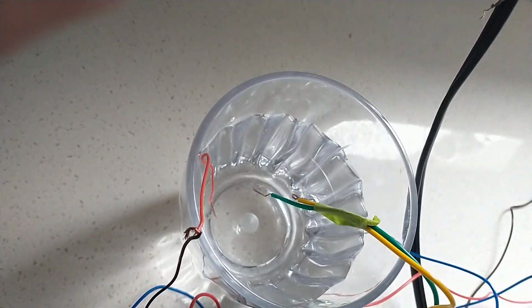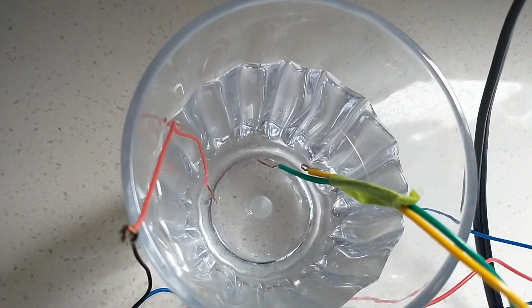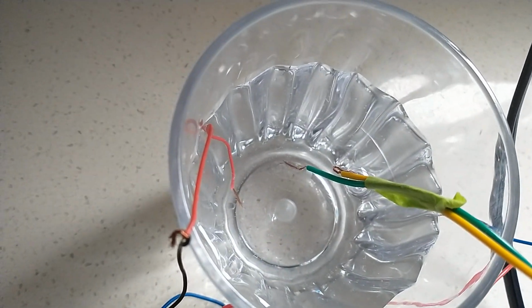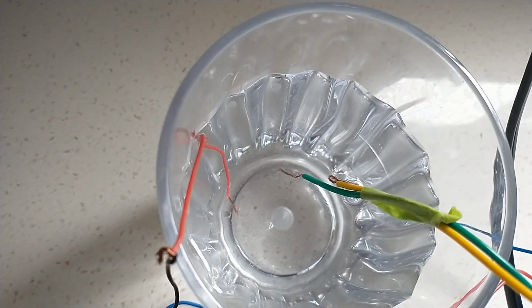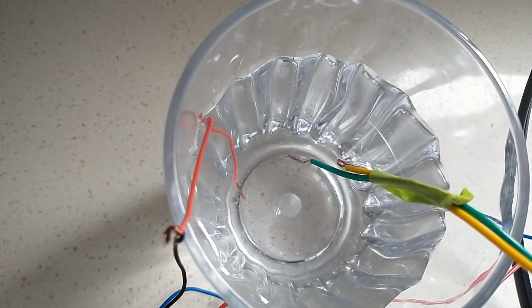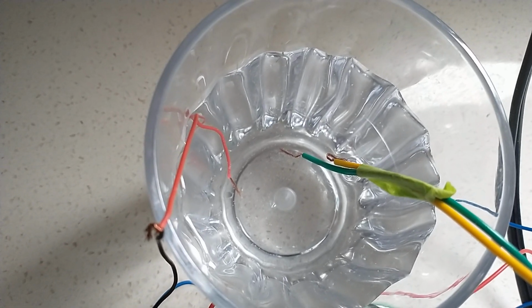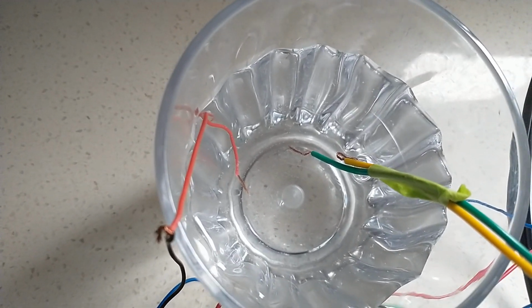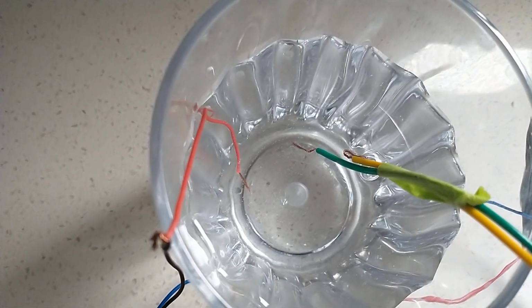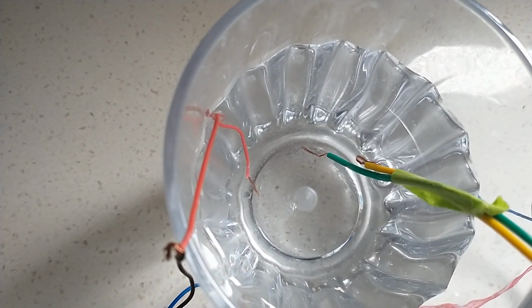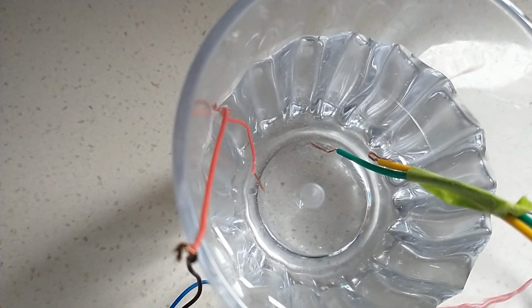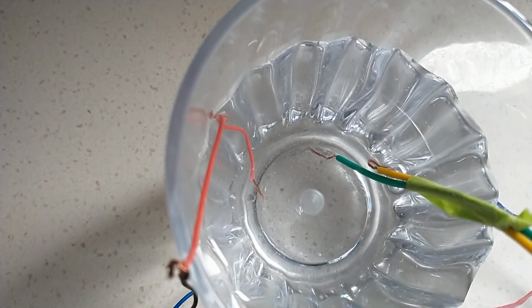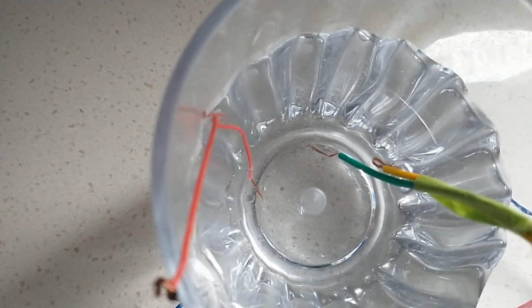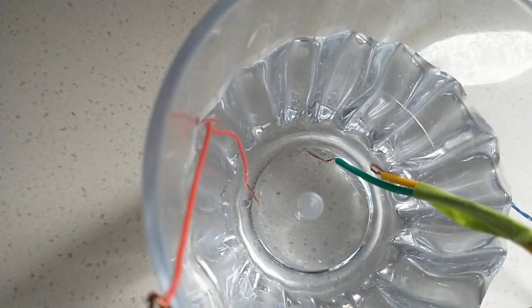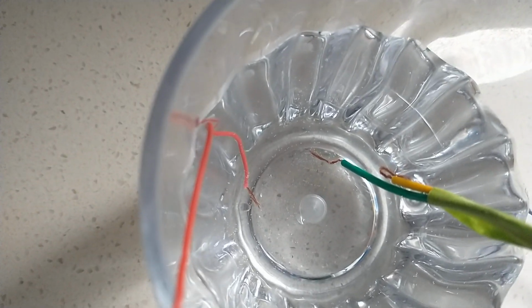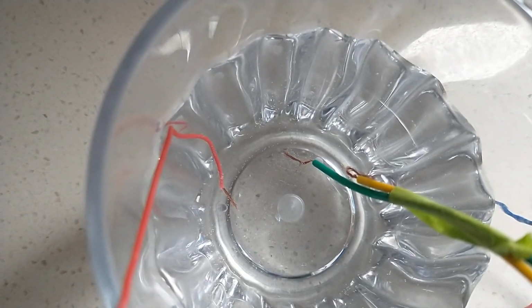But the yellow one, don't put it too high, and don't put it at the same level as the green one. Because if the water starts coming back from the city into your underground tank, as soon as it touches the yellow probe, the pump will start. If the pump is pumping at a higher rate than what is coming in, the water will go below the yellow and eventually below the green probe, and the pump will stop. Then as water comes in again and rises above the green, as soon as it touches the yellow probe, it starts pumping again.